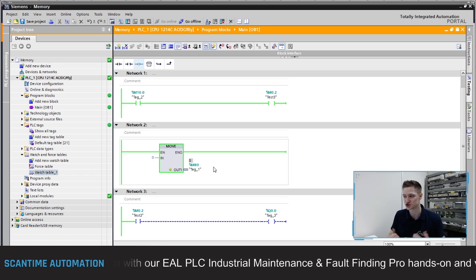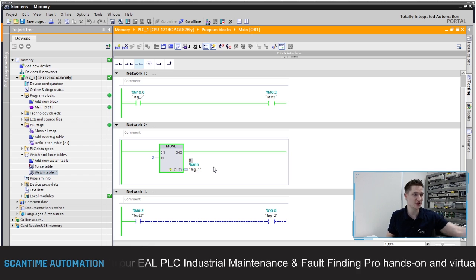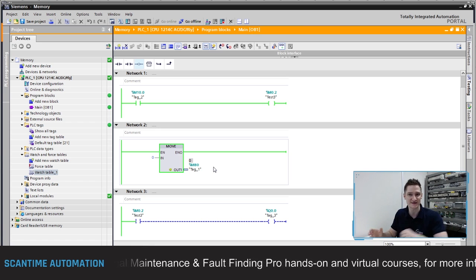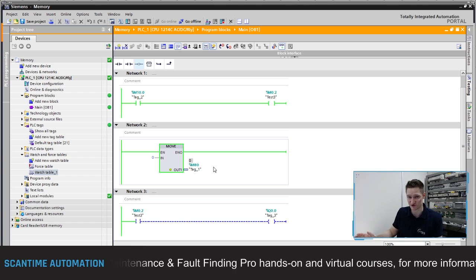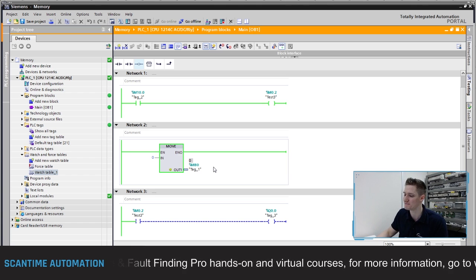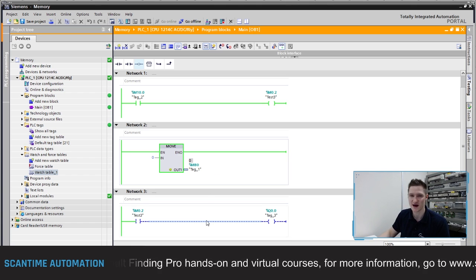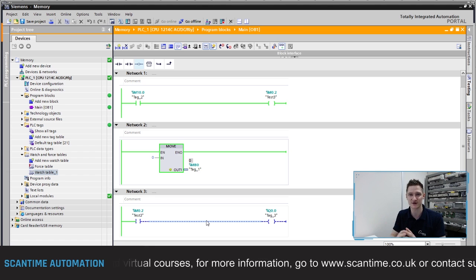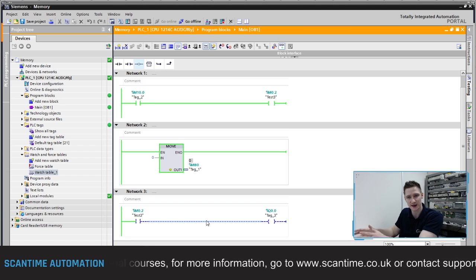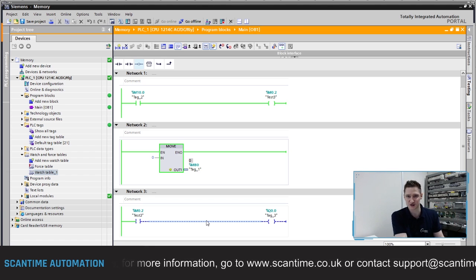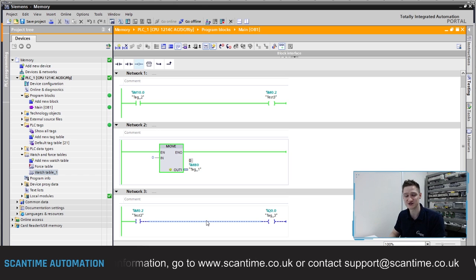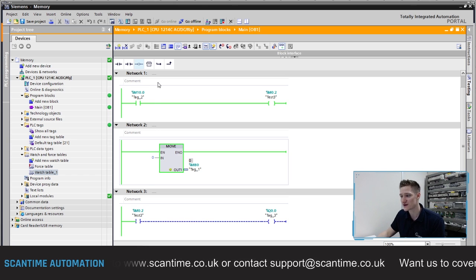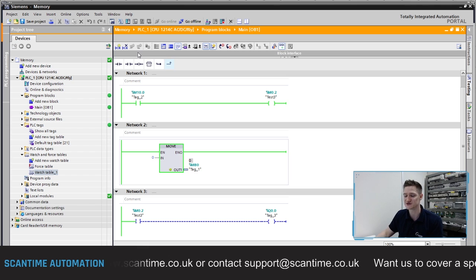You've got to be very careful with internal registers in Siemens, because it's very easy to assume: 'I'm using M0.0 here, so I can use MB0 separately' - but MB and M are not different, they're all part of the same memory area. It's not like Mitsubishi or Omron where they separate their memory areas into a whole collection for M bits and a whole collection for data registers. For Siemens it's all in one area.